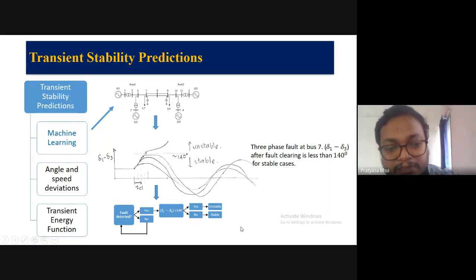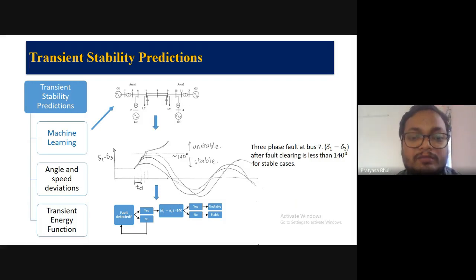So you can see that if any fault is detected, it will check delta 1 minus delta 3 after fault clearing. If it is more than 140 degrees, it becomes unstable. Less than 140 degrees, it becomes stable. So this is a very simple decision tree example. But in a realistic case, you have so many fault locations. Your operating condition will change. Your fault type will not be only three-phase. You will have different types of faults and different fault resistances. Your post-fault system may be different because some line may be tripped to clear the fault. So there will be so many cases, and the decision tree will not be that simple.